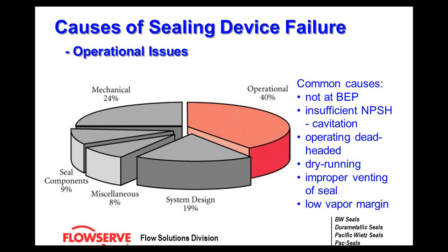Operating the pump dead-headed: oftentimes pump systems will be throttled somewhere in the system with a control valve. If you have a system designed for 200 gallons per minute but you need only five gallons per minute, you throttle down the control valve. This chokes off the pump, simulating a dead-headed operation, causing recirculation inside the pump case and building up heat, again causing a seal failure.